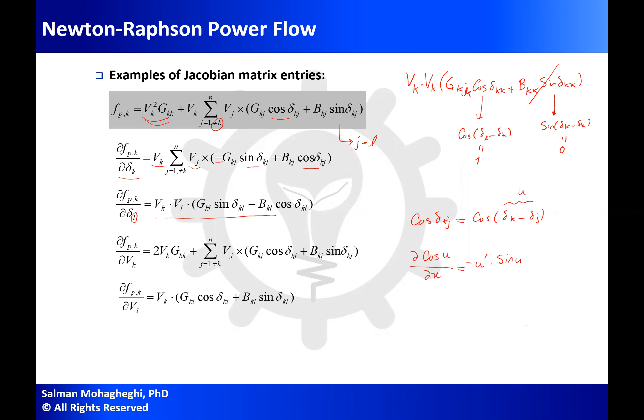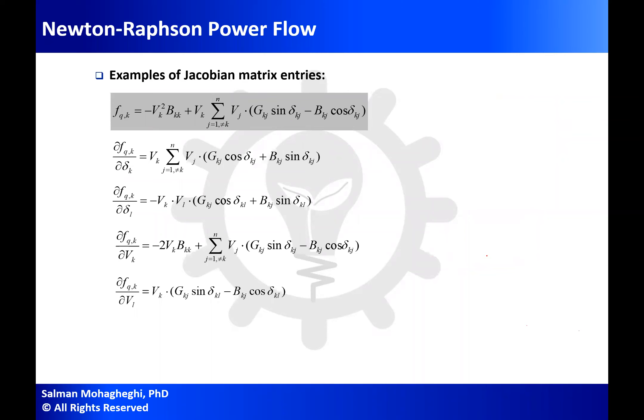Pay attention to sign: cos(δ_kj) means cos(δ_k - δ_j). Differentiating with respect to δ_k gives a U′ of +1, while differentiating with respect to δ_j gives U′ = -1 — so the signs will be different. Otherwise you'll get the wrong plus/minus signs. The same approach applies for F_Q: I take out the j = k term and find derivatives with respect to all deltas and Vs.